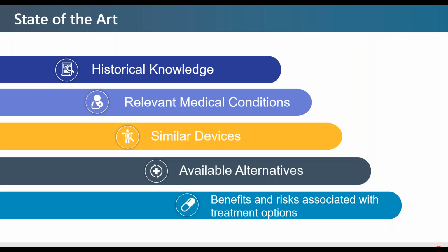So now the reason why I brought up equivalence first is because it's kind of a bummer that we can't use our competitors' devices as equivalents, but we can and we need to show those devices in the similar device section. We want to call out all of our competitors' devices and what their risks are, what their benefits are, what their clinical data is, to show that we're in line with that or we're better than that. And that's part of those available alternatives possibly, but maybe not.